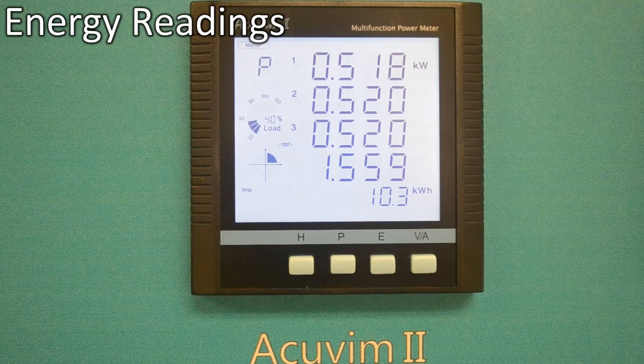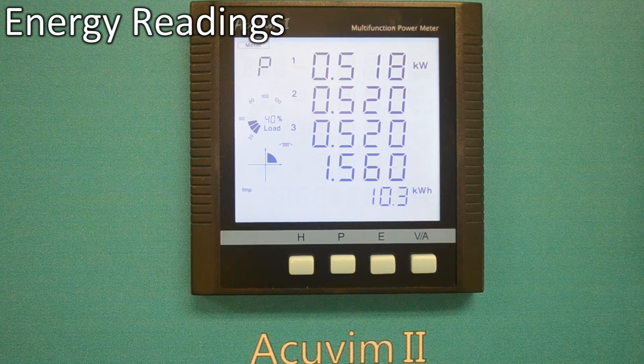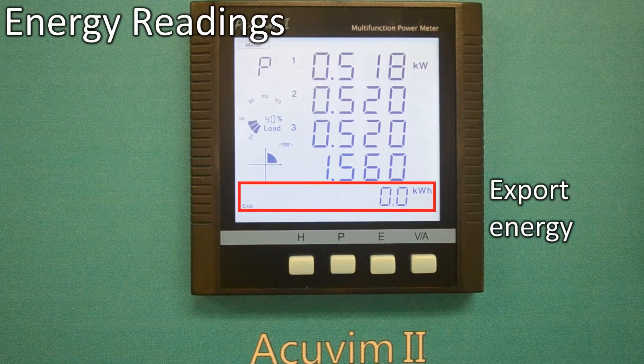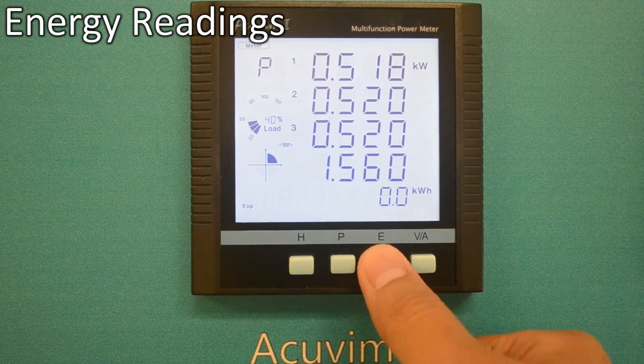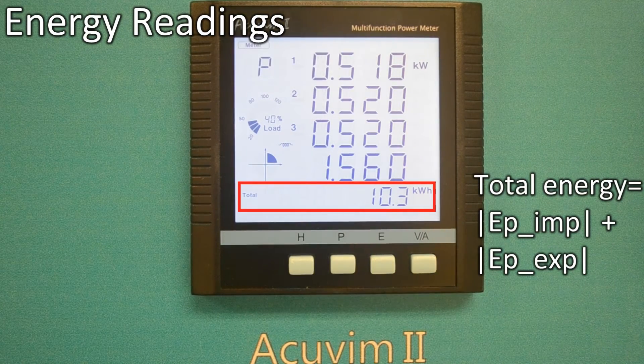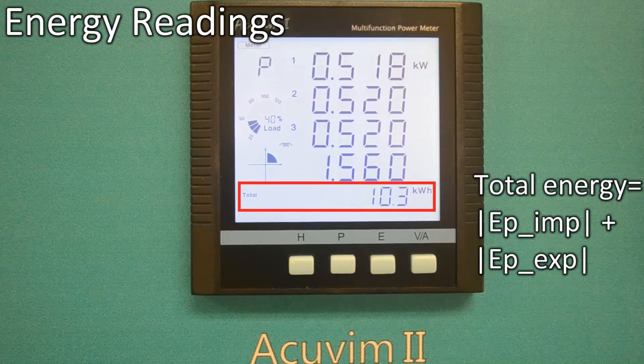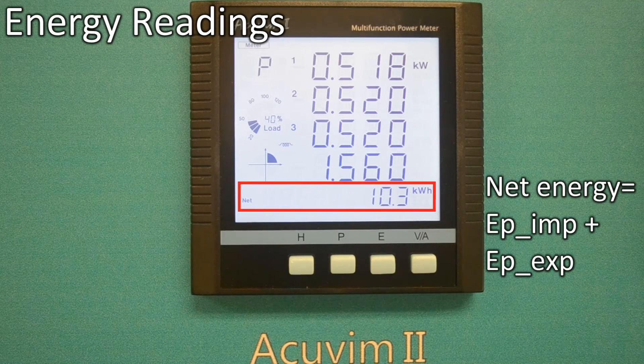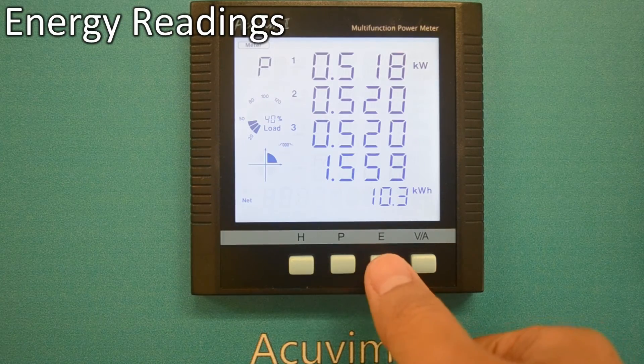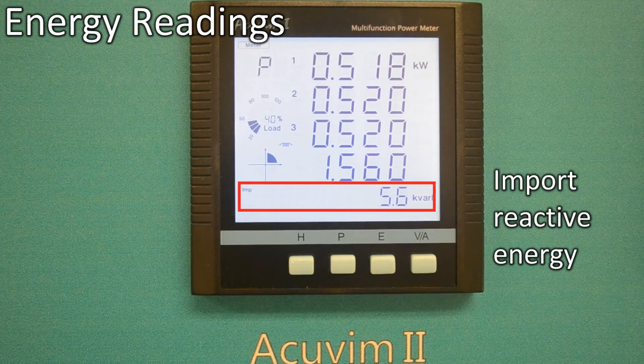By pressing the E key repeatedly, the meter will display EXP, which is export energy, or the generated kilowatt hour flowing from the load to the grid. Total energy is the absolute sum of import energy and export energy. Net energy is the algebraic sum of IMP and EXP energy.